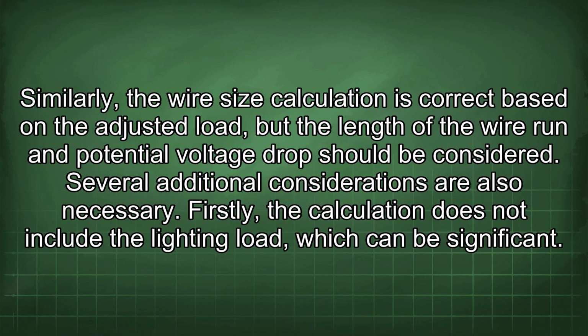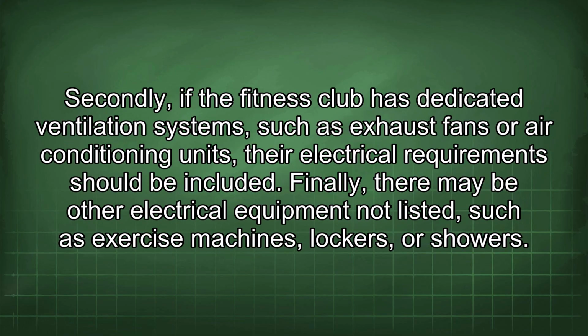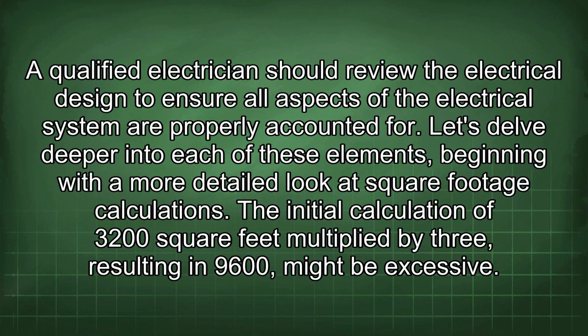Similarly, the wire size calculation is correct based on the adjusted load, but the length of the wire run and potential voltage drop should be considered. Several additional considerations are also necessary. Firstly, the calculation does not include the lighting load, which can be significant. Secondly, if the fitness club has dedicated ventilation systems, such as exhaust fans or air conditioning units, their electrical requirements should be included. Finally, there may be other electrical equipment not listed, such as exercise machines, lockers, or showers. A qualified electrician should review the electrical design to ensure all aspects of the electrical system are properly accounted for.